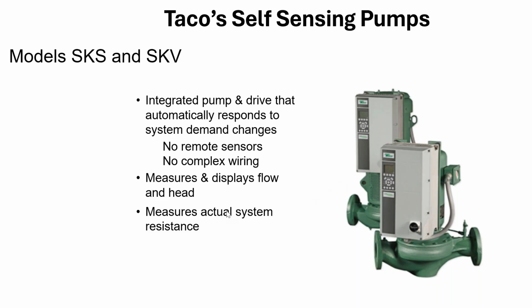And we're going to get into that a little more, but think about that. Most of the time on most projects, right? If you design for 80 feet of head loss, there's a good possibility, I'm talking 80-90% of the time, if not more, that head loss is probably less in the field. Well, here's a big thing here, and we're going to talk about how these drives in our system allow you to take advantage of that, so you can run this pump at a lower speed to actually respond to that. So if you got 200 GPM at 80 feet, and instead it's actually 200 GPM at 70 feet, you can actually reprogram the drive to run it on that system curve instead. And we'll talk about that a little more.